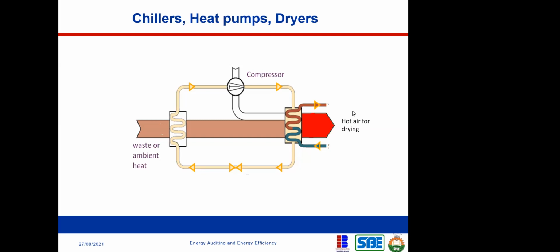Then you now pass water, or hot air for drying. This could be hot air, it could be water. But in this case, they use air. So it's air to air, not air to water. The first example I cited was air to water, but in this case it's not passing water. So you pass another air to extract the heat from this low-grade ambient air. You now pass another air through the tube.